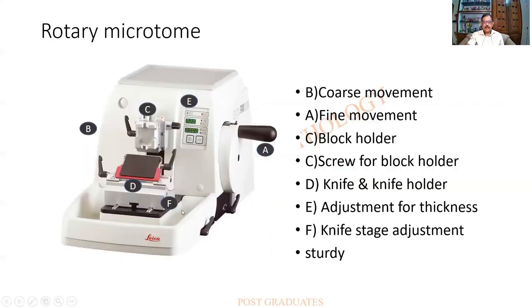This picture is of paramount importance — students should follow it meticulously as questions may be asked about it. This is a very sturdy modern rotary microtome from Leica; there are two versions — semi-automatic and automatic. The automatic version has a motor attached, and once switched on it advances through the set distance automatically.